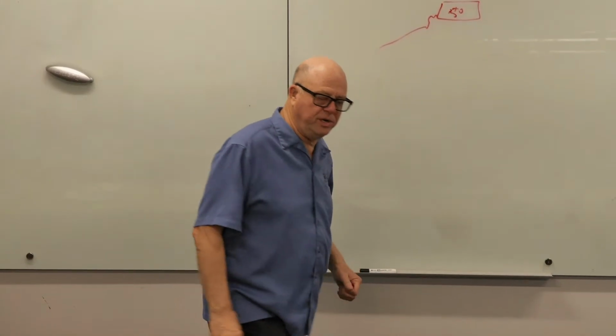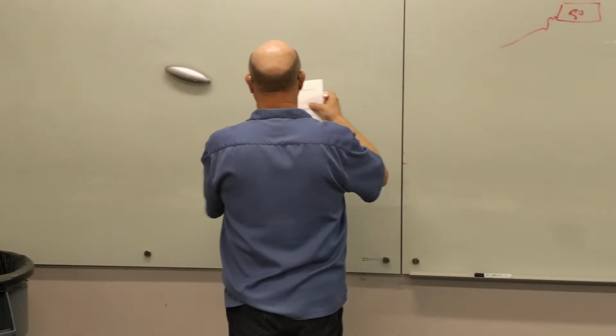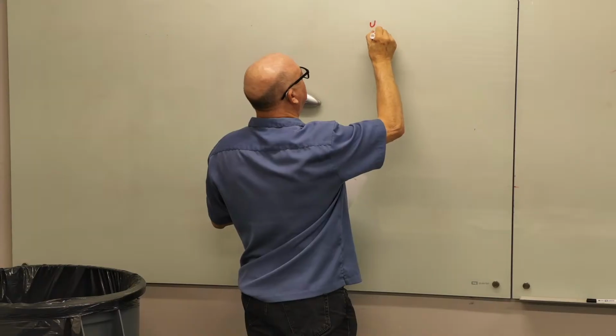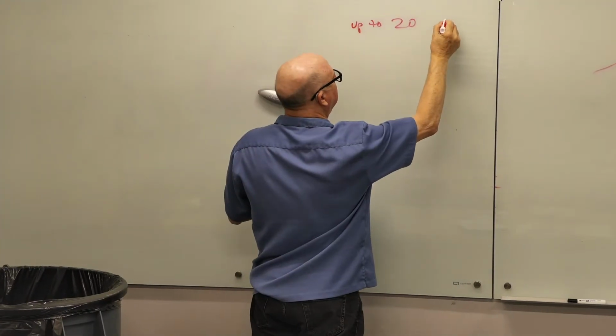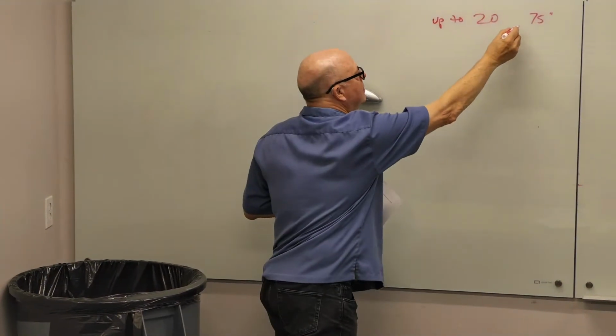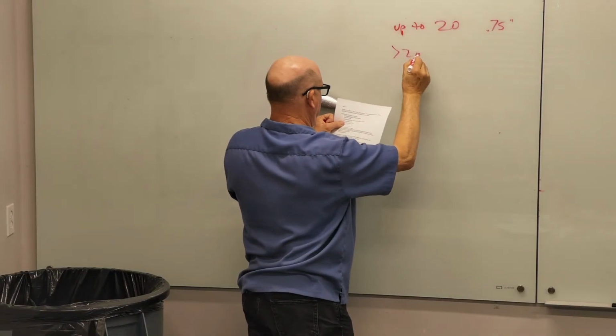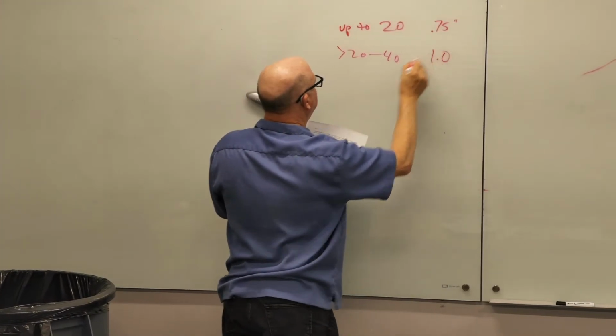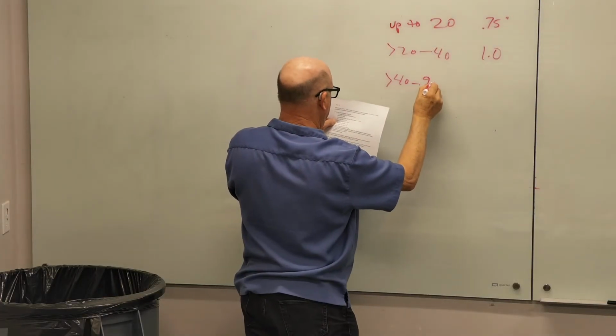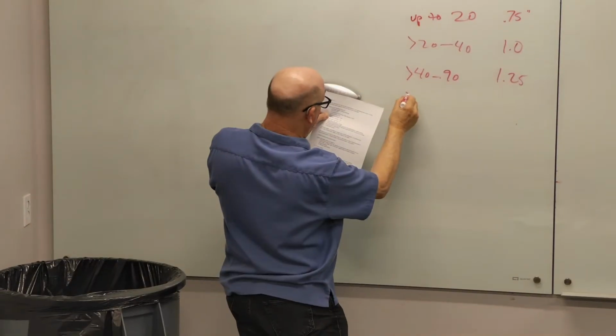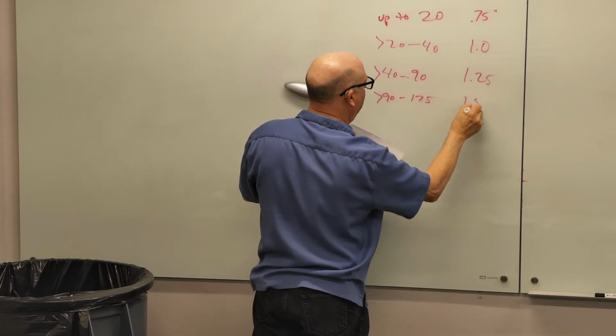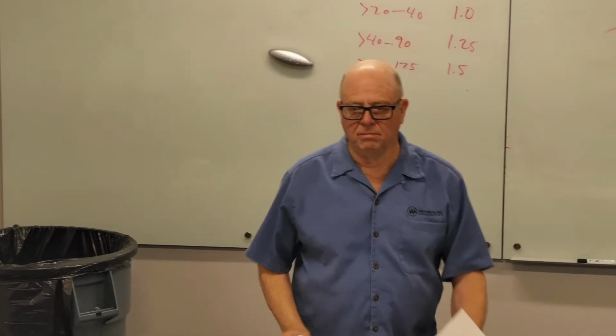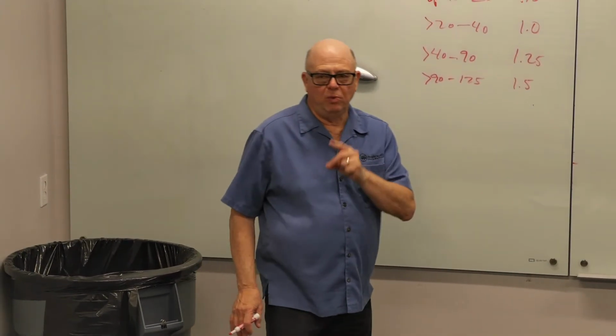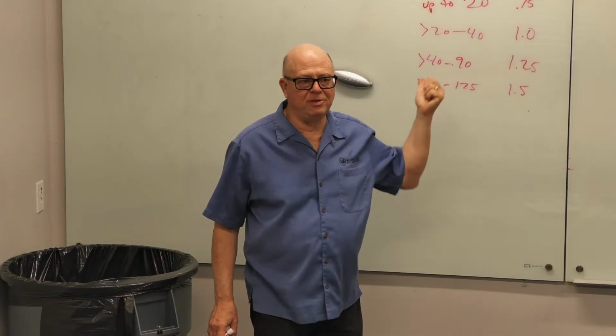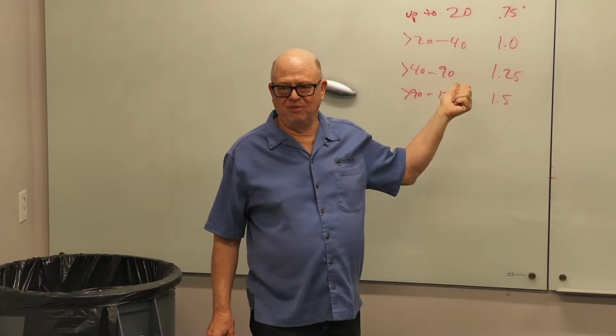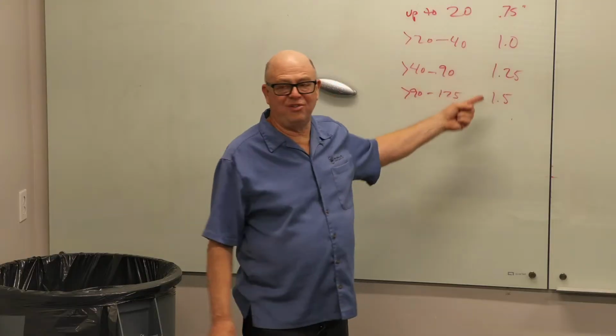Well, when you look at condensate draining sizes, if you're up to 20 tons, you're supposed to have a 3/4 inch condensate drain line. If you are greater than 20 tons, up to 40 tons, it's 1 inch. If you're greater than 40 tons, up to 90 tons, it's 1.25 inches. And if you're greater than 90, up to 125, it's 1.5 inches. You're not likely to see much bigger than that, so I'll leave it there. Well, we went from 40-ton to 50-ton units, didn't we? What happens to the code condensate drain size between 40 and 50 tons? It goes from 1 inch to 1.25 inches.